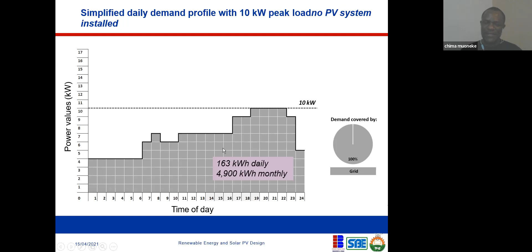If you check that by month, you have 4,900 kilowatt hours of energy. But we don't want to cover all of this energy with the solar system. So if you integrate that solar system into this, remember it is an 8 kilowatt peak solar system, it becomes a very good design because your peak is around 10 kilowatts, and your solar is doing just about 6.